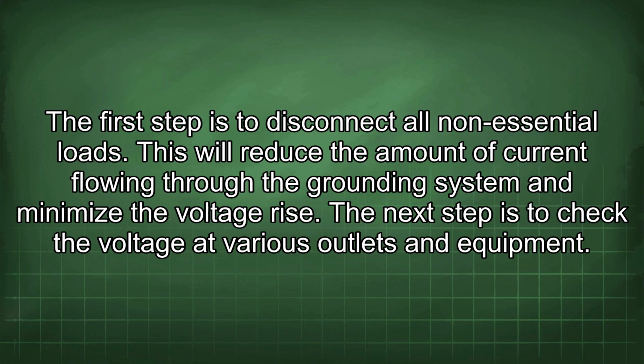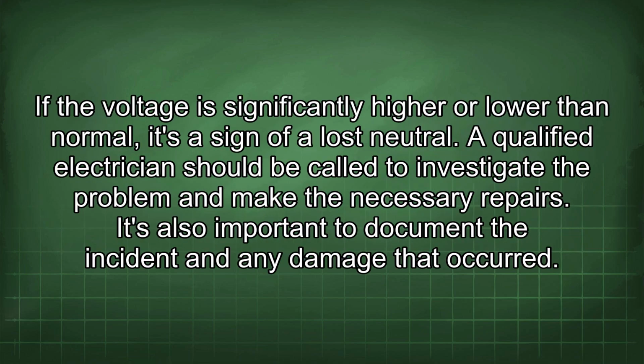SPD should be installed at the service entrance and at branch circuits that serve sensitive equipment. In the event of a suspected lost neutral, it's important to take immediate action to prevent damage to equipment and ensure safety. The first step is to disconnect all non-essential loads. This will reduce the amount of current flowing through the grounding system and minimize the voltage rise.